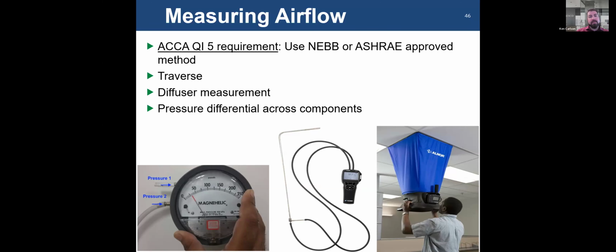There's a lot of leeway in houses. Doors are open. There's migration of temperature and everything like that, of air. So there's a lot of leniency, but in theory, each diffuser that you set should have the required amount of airflow based on your Manual J calculation. There's a few methods of measuring the airflow. All right. So that bottom right is a balometer.